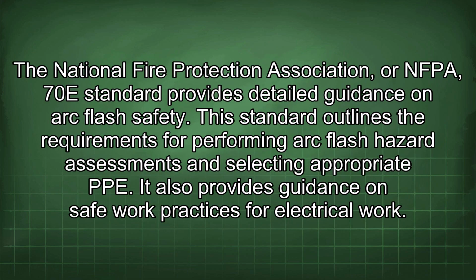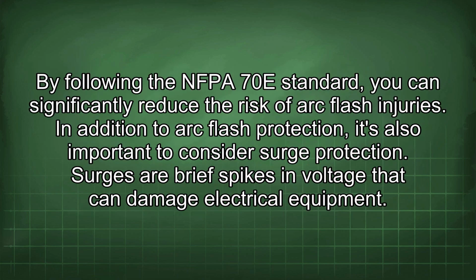The National Fire Protection Association, or NFPA, 70E standard provides detailed guidance on arc flash safety. This standard outlines the requirements for performing arc flash hazard assessments and selecting appropriate PPE. It also provides guidance on safe work practices for electrical work. By following the NFPA 70E standard, you can significantly reduce the risk of arc flash injuries.